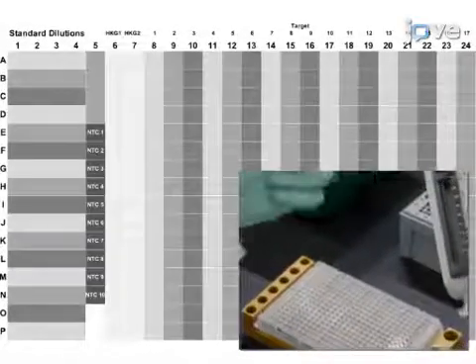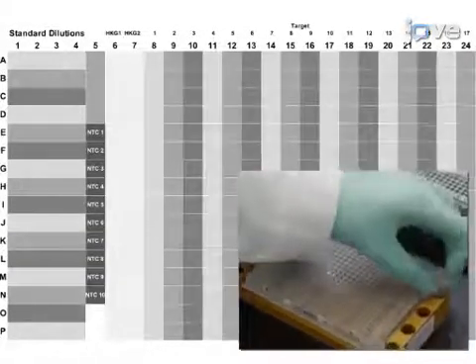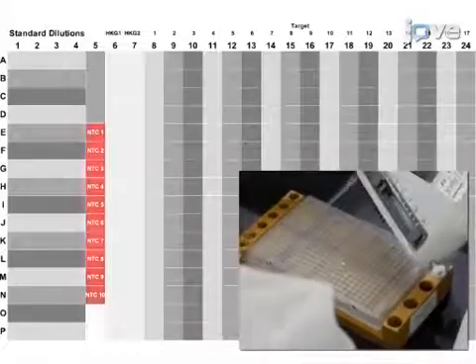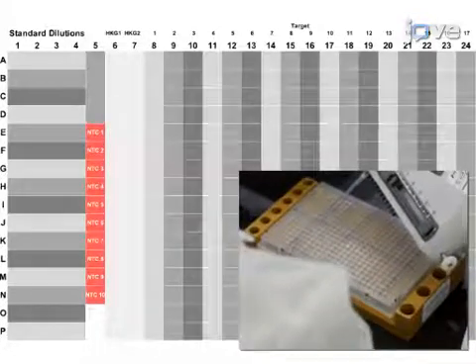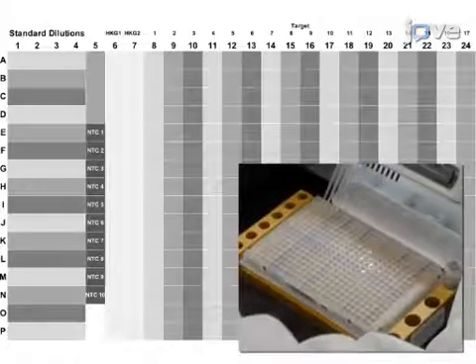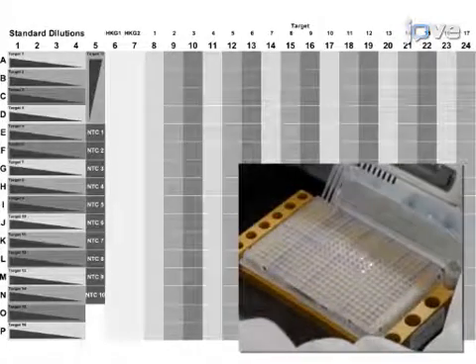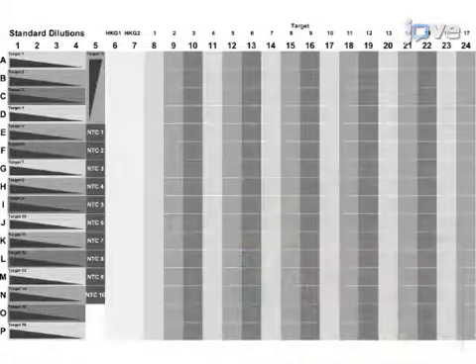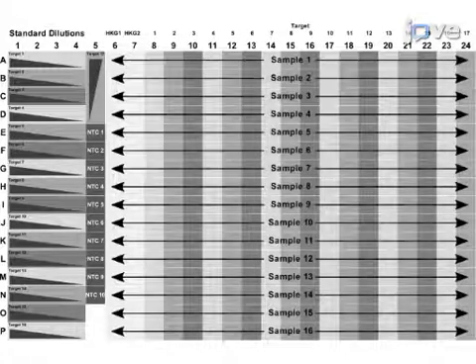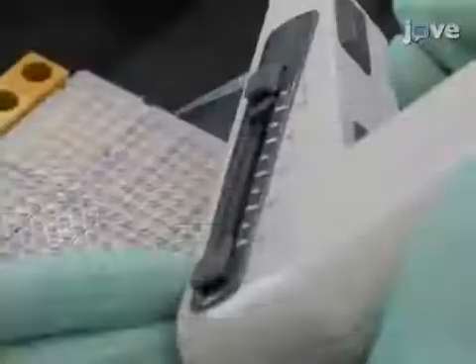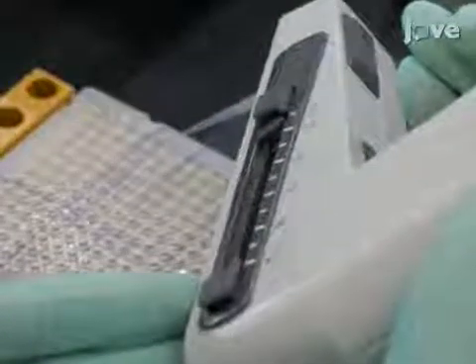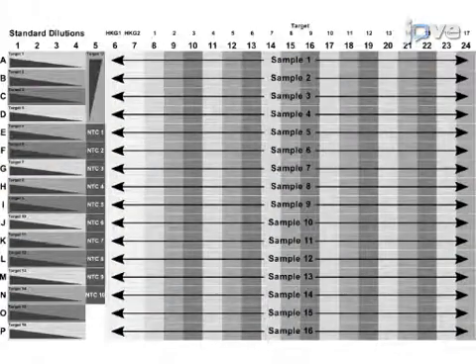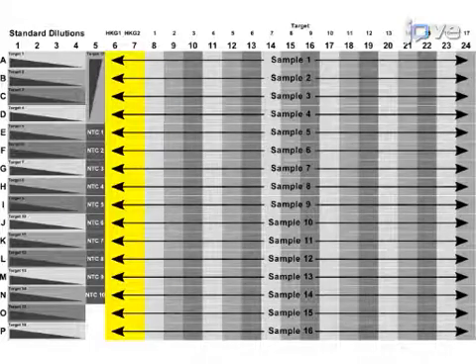With the 30 microliter electronic multi-channel pipette, dispense 7.5 microliters of NTC well mix to each NTC well. Dispense 6 microliters of the standards well mix and 1.5 microliters of the standard to each standard well. Then dispense 7.5 microliters of the sample to the designated wells. With a 12.5 microliter electronic multi-channel pipette, dispense 2.5 microliters of the HKG primer probe mixes to the designated wells.